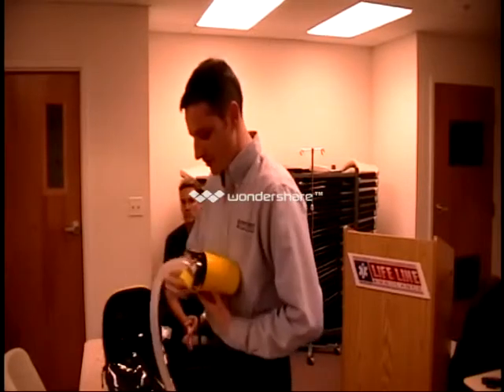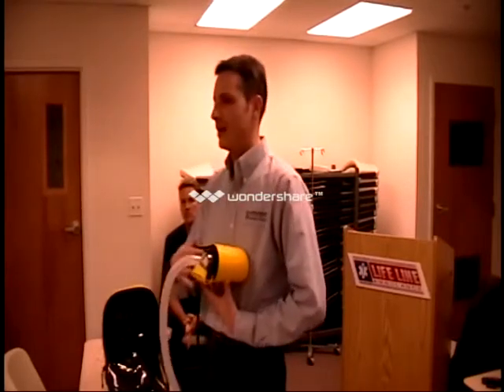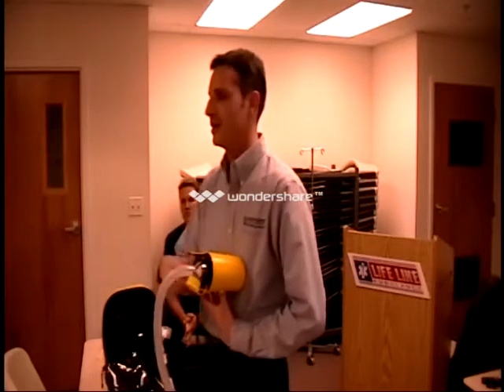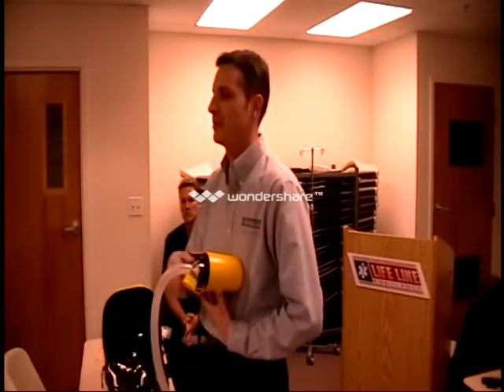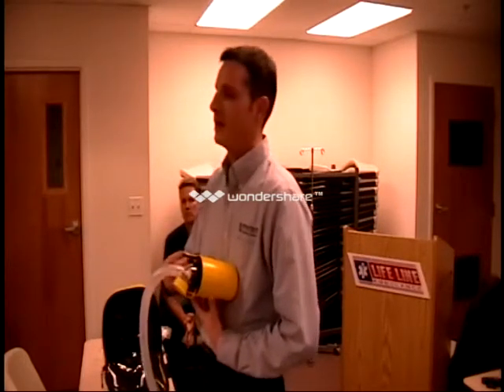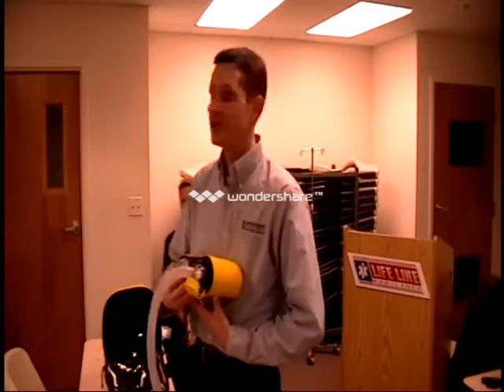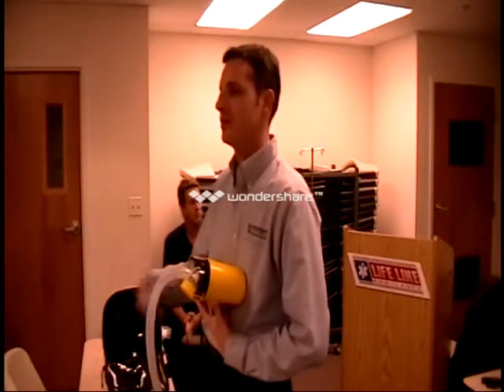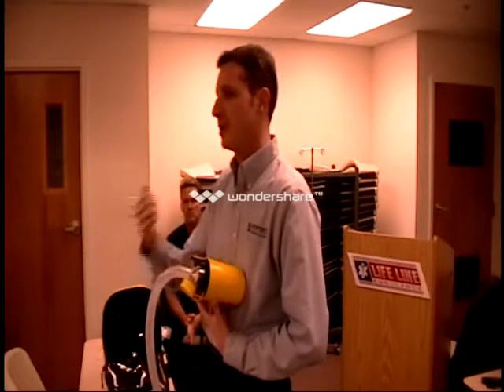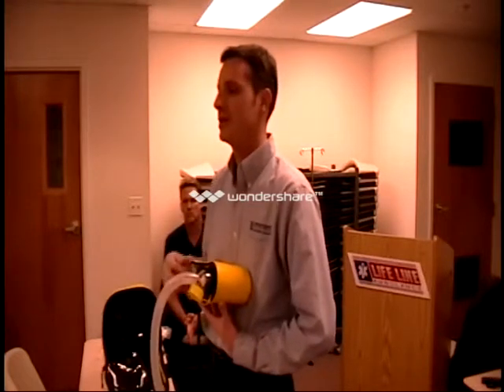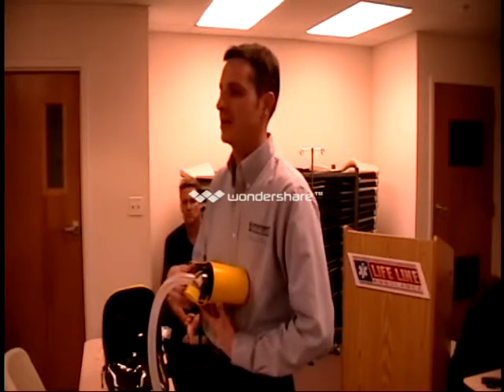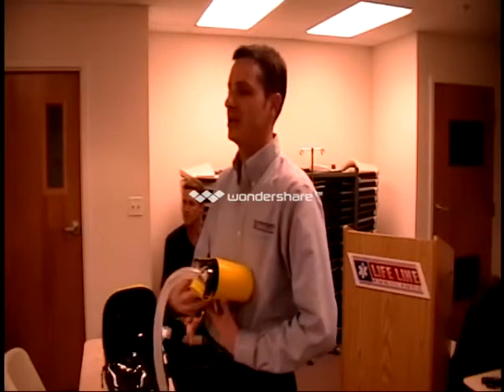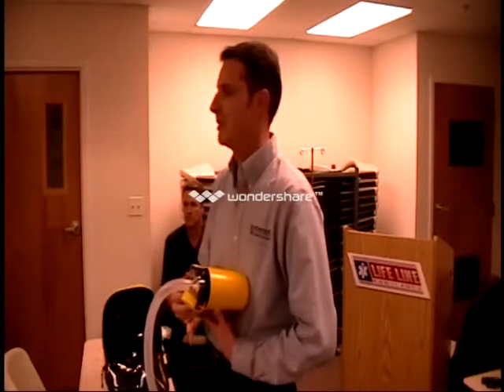The range of motion for this regulator here is not the green. The green just shows you which direction it can turn. It actually will take 3 full turns to get all the way up to max pressure. It takes about a half turn to even get it started. On the procedure I was talking about, you give it a half turn, it starts to flow a little bit. As it's flowing, you put it on the patient, and titrating is just starting to turn this and monitoring where that needle sits on exhalation. Simple as that. You put this on the patient, and they breathe as you're turning this pressure up for them.